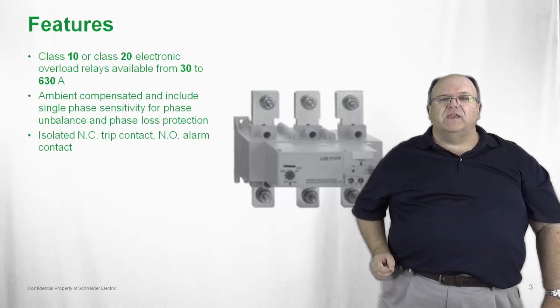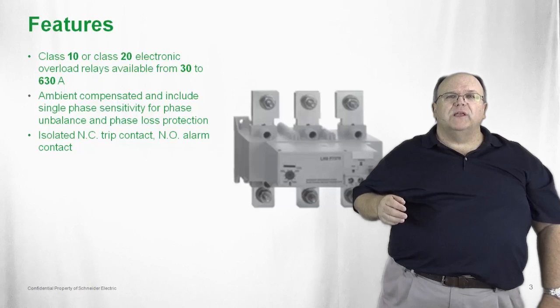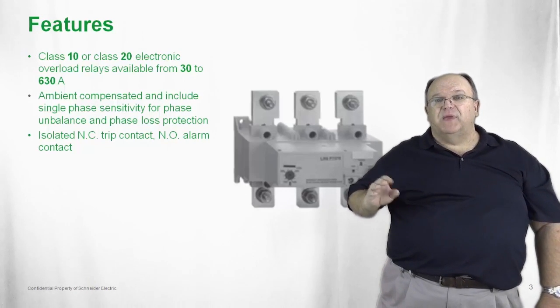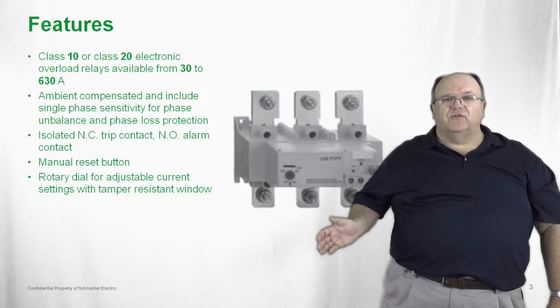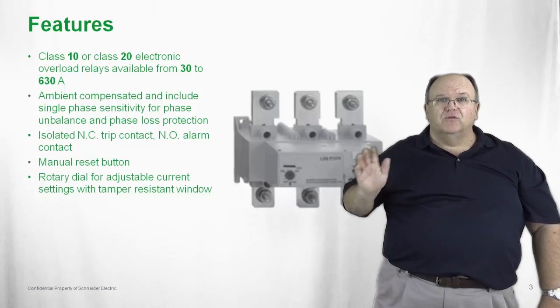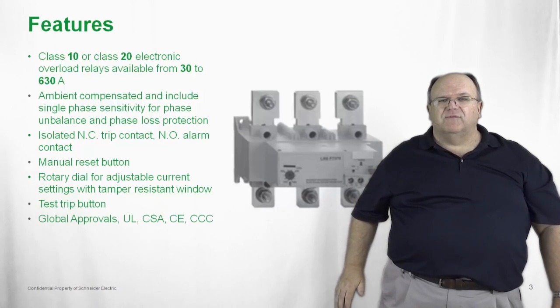The overload also has a normally open and a normally closed auxiliary contact. The normally closed contact is typically associated with a control circuit, while the normally open contact is associated with an alarm circuit — whether it be a light, a bell, or a buzzer — passing along information on motor status. The LR9F also includes a manual reset button and a rotary dial that's very easy to set: just dial in the motor full-load amperage, close the tamper-resistant window, and lock those settings in place. It mounts directly to the TeSys F contactor.